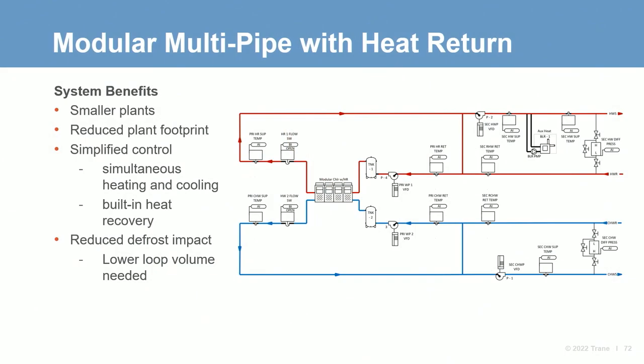Now, for applications with smaller loads and significant simultaneous heating and cooling hours, multi-pipe heat recovery units can reduce plant footprint and simplify system controls. Unit-based control modes include cooling only, heating only, and simultaneous heating and cooling, and do not require added system valve control. And with a higher number of relatively smaller refrigerant circuits, the impact of defrost cycles is less than packaged chillers. Again, related system design strategies and tools will be discussed in a future E&L.